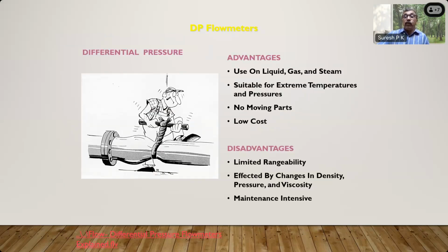These are used for liquid, gas, and steam applications, and are suitable for extreme temperatures and pressures. There are no moving parts and the initial cost is low, but the rangeability is limited. That is, you get accurate measurement only within a range. If you are selecting for up to 100 cubic meters per hour, the range is 100 to 30. That is limited rangeability. The measurement is affected by changes in density, pressure, and viscosity. Maintenance will be intensive. These are the disadvantages.